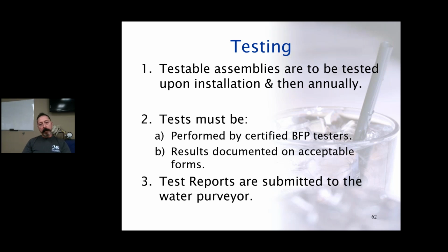Test assemblies are basically done on a test report and submitted. Somebody will document the functionality of those, to ensure they're functioning properly. They have to be performed by a certified backflow assembly tester, and the results, again, documented on the acceptable form.